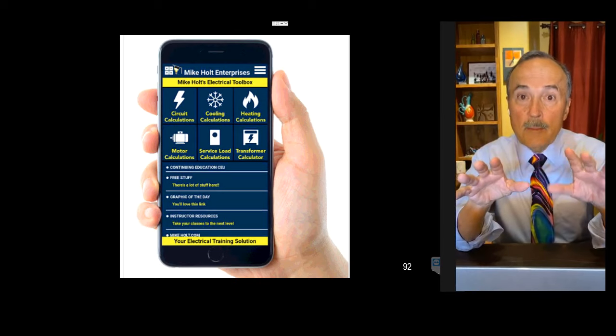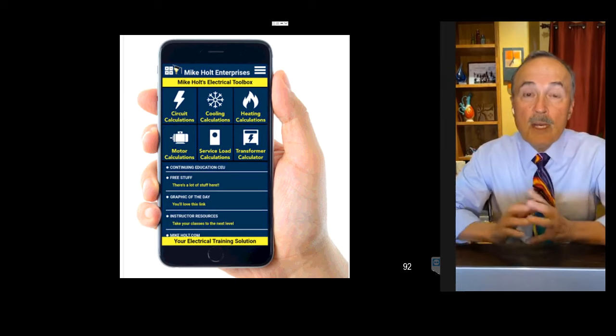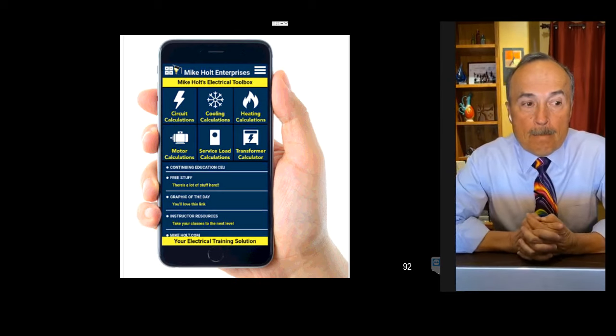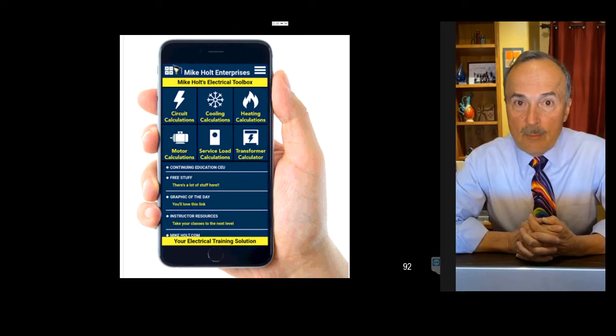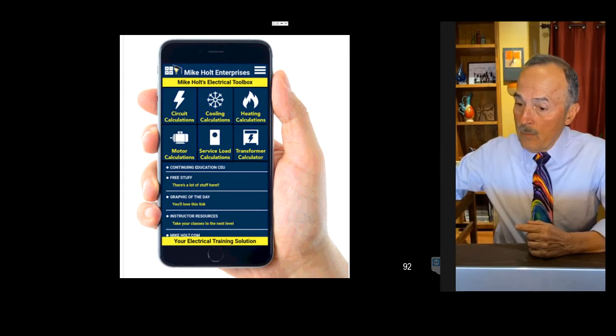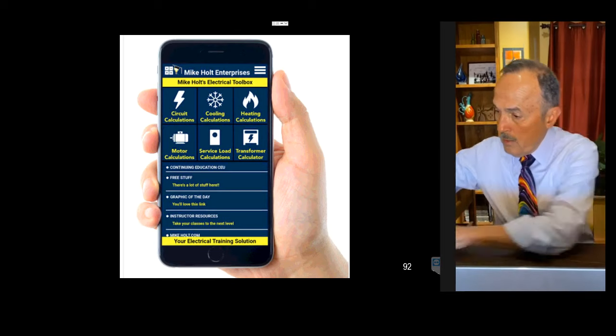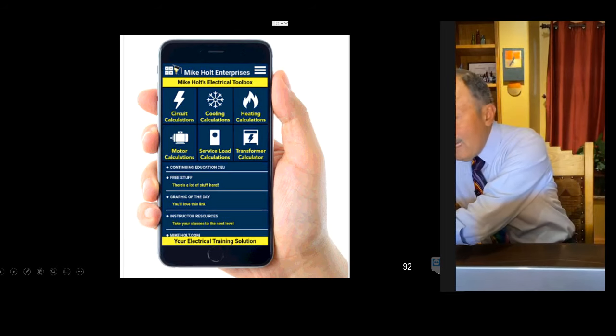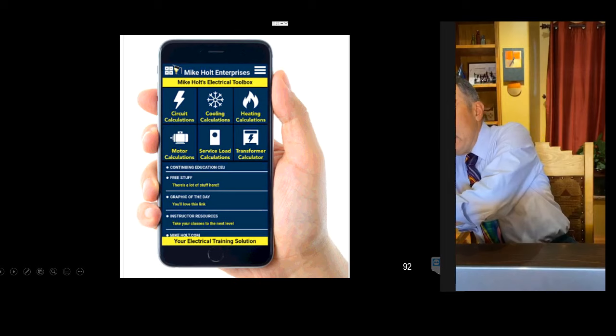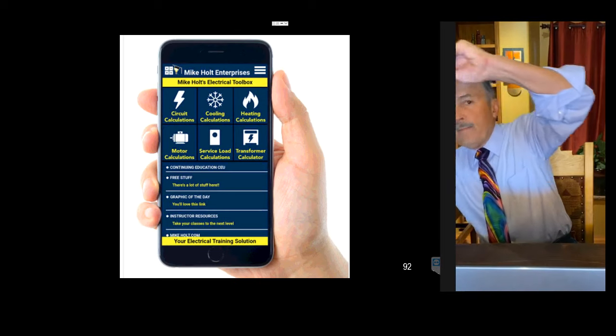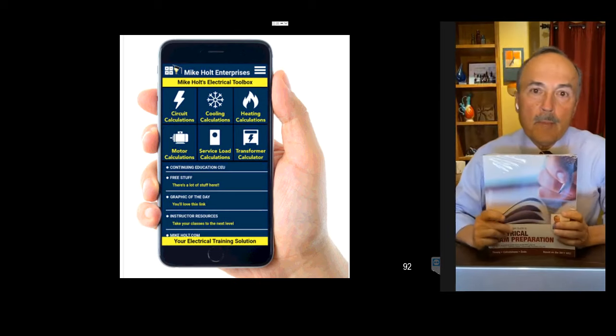It tells you the size of the service disconnecting means and the size of the overcurrent protection device. It gives you the service conductor size, the neutral conductor size, the grounding electrode conductor size, and what size raceway. It gives you everything, and it's free. But I still had a question, by the way. You should never depend on software. You should know exactly how that residential load calculation is done, because if you're going to take a test, you're not taking my app in there. Okay? So you need to actually know how to do it.